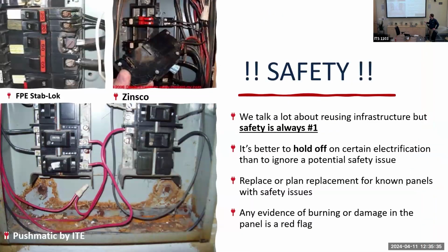When we talk about trying to keep some of the existing 100 amp service panels or less, and kind of tricking the system into allowing us to meet the load calc, we still need to keep safety in mind through all of this. If we walk in and see a panel that's just garbage, evidence of burning or melted bus bars or something, we have to take care of that and fix it.